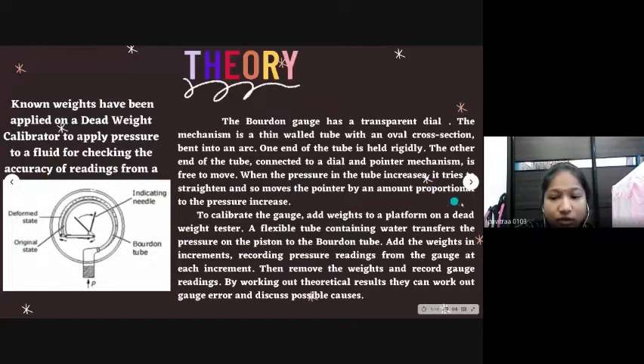To calibrate the gauge, add weights to the platform on the dead weight tester. The weights put a known force onto a piston. The piston has a known area, so we can calculate the pressure, and a flexible tube containing water transfers the pressure on the piston to the Bourdon tube. Add the weights in increments, recording pressure readings from the gauge at each increment. Then remove the weights and record gauge readings. By working out the theoretical result, they can work out gauge error and discuss possible errors. Next page.